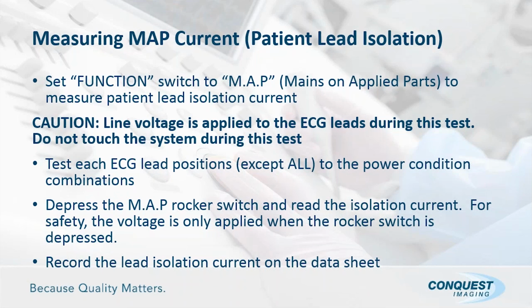You want to test each ECG lead to the power condition combination. Again, they say except ALL. You want to depress a MAP rocker switch and read the isolation current. Now that's when you depress it, that's when the line voltage is applied. So that's when the system is in its most unsafe condition. So be careful where your hands are. If there's somebody working with you, you need to be aware of where they're at on this. And at that point, record the lead isolation current on the data sheet.